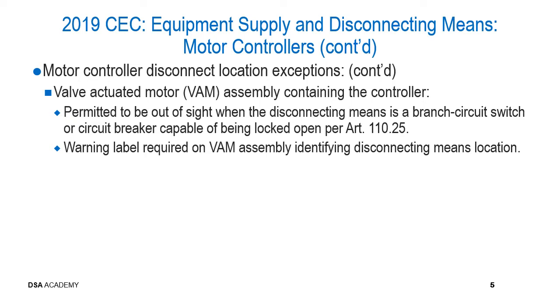Continuing with the exceptions for disconnects required to be located within sight from the motor or the motor controller. In situations where you have a valve actuated motor assembly that contains the controller, the disconnect is permitted in these situations to be out of sight when the disconnecting means is a branch circuit switch or a circuit breaker, again, capable of being locked in the open position in accordance with Article 110.25. Additionally, a warning label is required to be mounted on the VAM assembly, identifying the location of the disconnecting means.